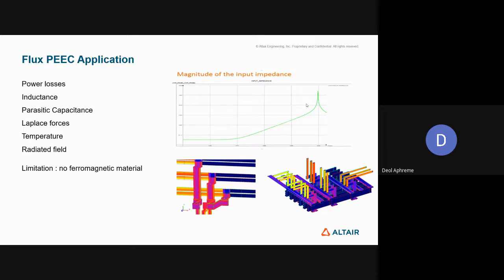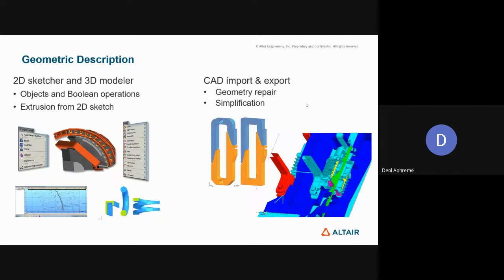And even though it seems fairly simple, like you could just randomly place three bus bars and send current, or send power across it, the position of bus bars with respect to their faces, as we all know, makes a big difference. If they are not spaced correctly apart, the mutual inductance, just like how power lines interact with each other, even bus bars interact with each other. So it's very important to understand what would be the input impedance and the output impedance, which dictate the power flow, while designing these components.